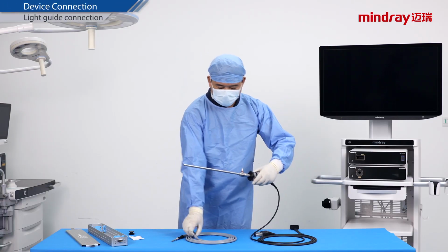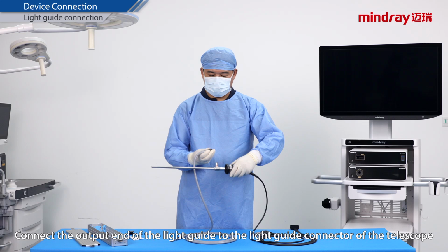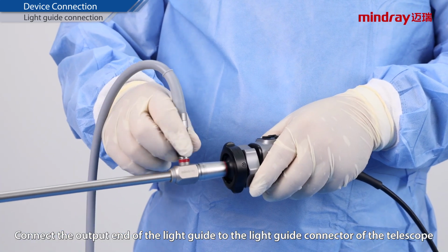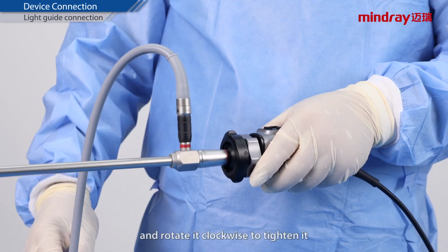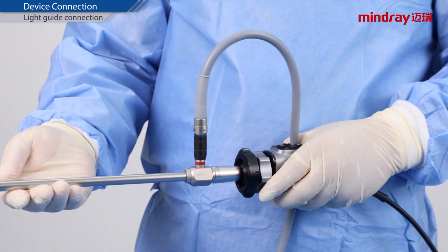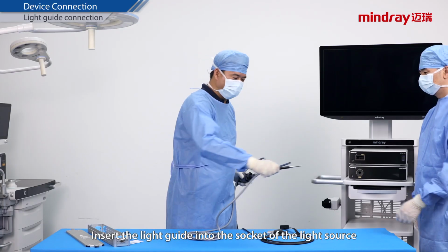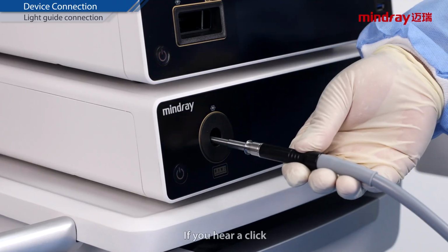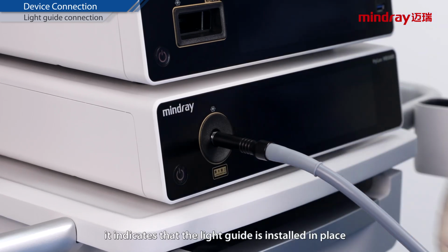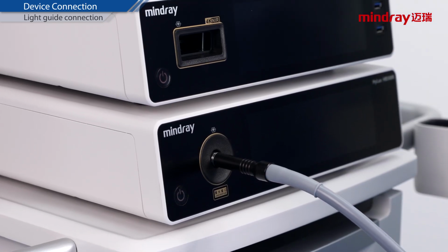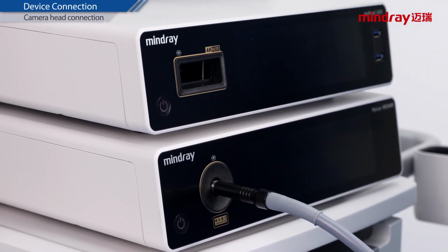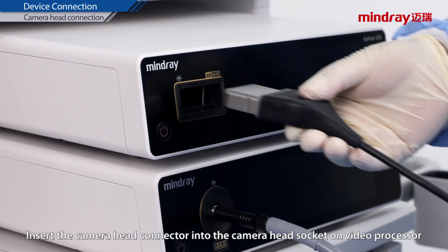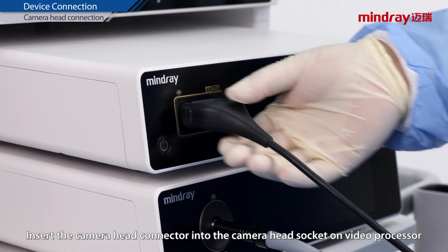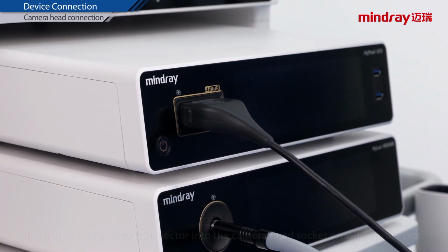Light guide connection. Connect the output end of the light guide to the light guide connector of the telescope and rotate it clockwise to tighten it. Insert the light guide into the socket of the light source. If you hear a click, it indicates that the light guide is installed in place. Camera head connection. Insert the camera head connector into the camera head socket of the video processor.